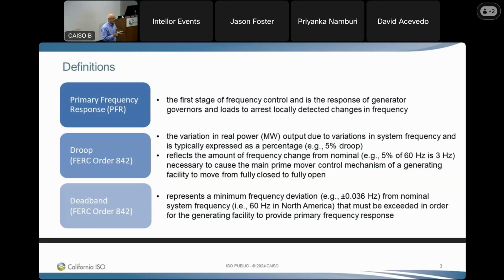They can give you more energy if the frequency were to drop. So it becomes absolutely critical that we get our battery storage and other fuel types that have some capacity to give us frequency response right, in order to maintain the reliability of the interconnection. That's why we're actually paying a lot of close attention to battery right now, because we're getting a lot of it coming onto the system. And as you will see, we're not getting a consistent response from these units.